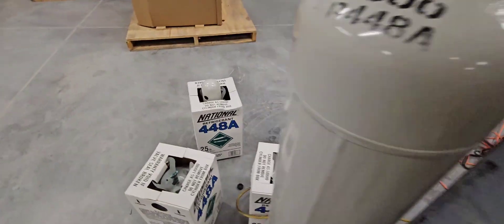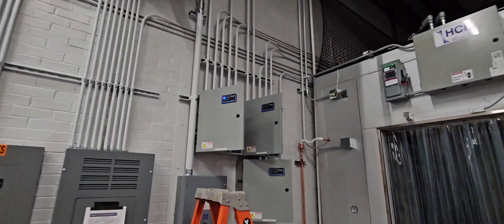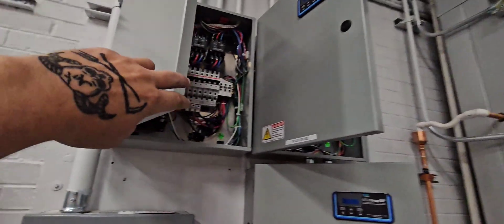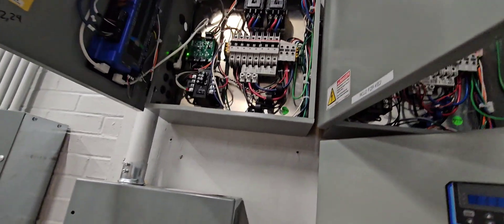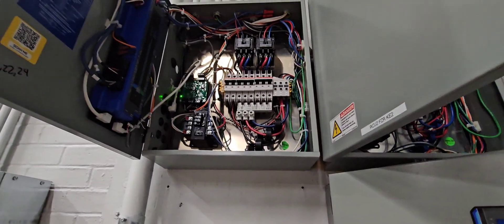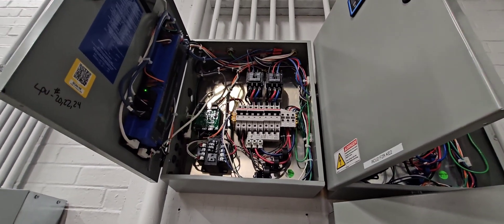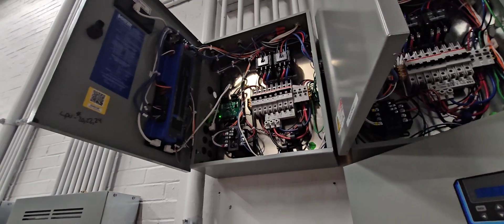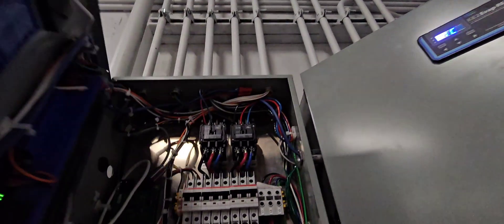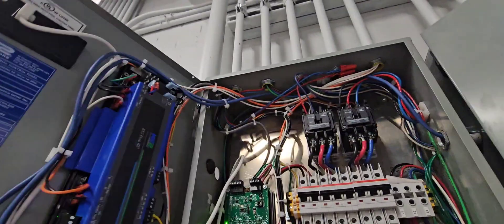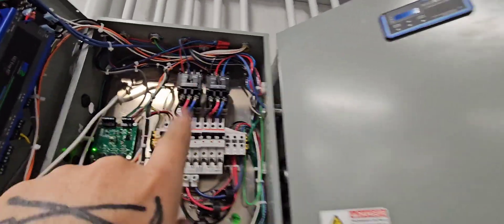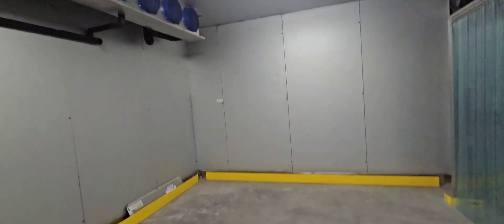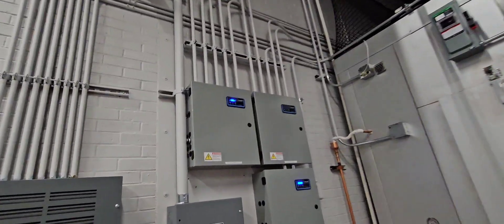I definitely have more than what we need which is fine. So what we need to do over here is need to program this but first we're going to turn off power and then hook up those solenoid wires that way we can get that thing running and then basically just watch it run, check all the measurements and everything and call it a night. We got this thing all programmed, got the solenoid wired back in. Everything's running. I've already checked defrost. And you can see everything's running in here. I hear it feeding. Just got to go back up on the roof and check to make sure that the compressor is not short cycling or anything.